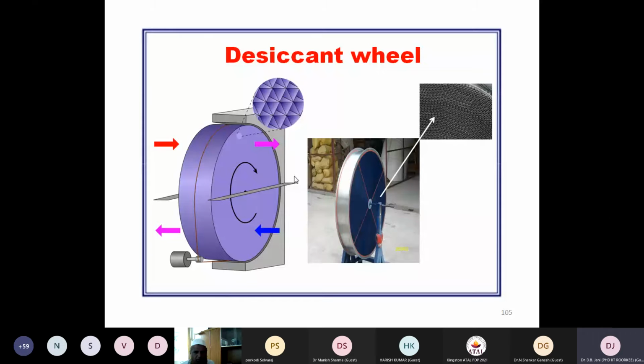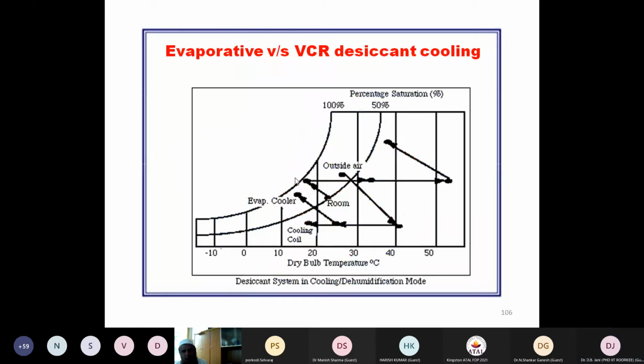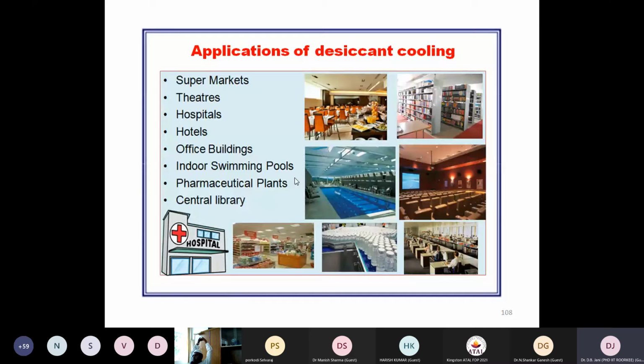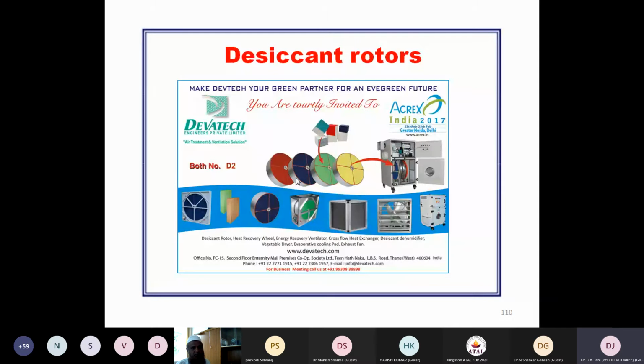This is how the desiccant dehumidifier looks internally, its matrix, and how it gets laden with the desiccant material to create a maximum surface area internally through the sinusoidal or honeycomb structure, so that the maximum desiccant material can be stored or lined within the flutes of the matrix. These are typical applications with either a large area or human occupancy, where desiccant cooling will find prolonged application, such as a supermarket, theater, hospital, hotels, office building, indoor swimming pool, pharmaceutical plants, central library, all where dehumidification as well as cooling will be required. There are typical dehumidifier manufacturers in India and abroad, from whom you may collect or construct your wheel according to the requirement of your experimentation.